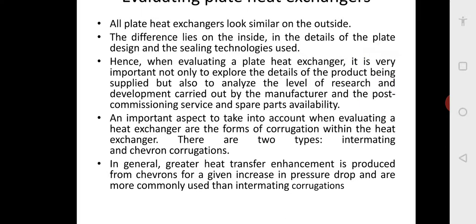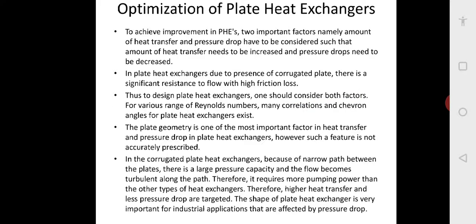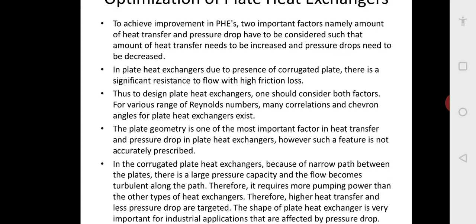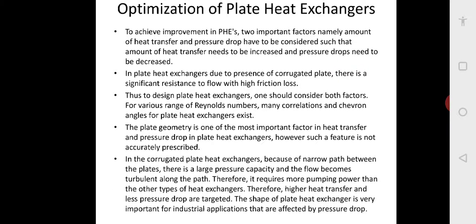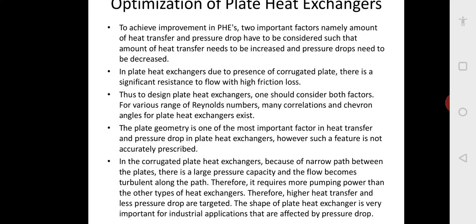There are two types of corrugations: intermating and chevron corrugations. Greater heat transfer enhancement is produced by chevron corrugations for a given pressure drop, so they are more commonly used. Because the gap between plates is small, there is a pressure drop. To improve plate heat exchangers, two important factors must be considered: the amount of heat transfer needs to be increased and the pressure drop needs to be decreased. Due to corrugated plates, there is significant resistance to flow with high friction loss, so both factors must be considered in design.